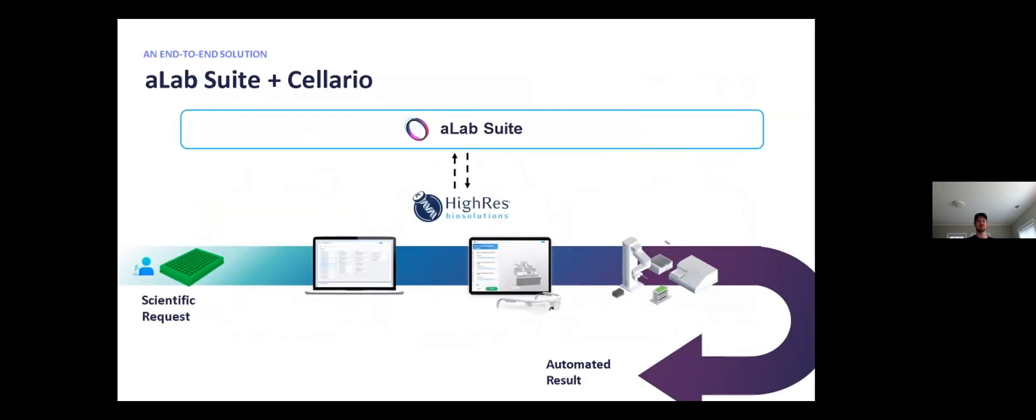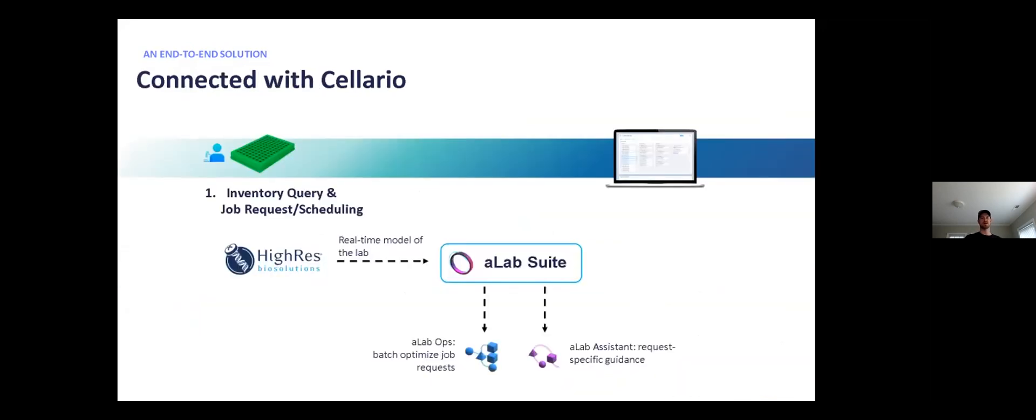So now that you have an understanding of how A-Lab Suite works as a whole, we'll dive into the specifics of how A-Lab and Cellario work together to drive automation. To start, when a user batches or schedules a job in A-Lab, the first thing we need to do is understand the state of the work cell. We do this by using the Cellario services API to query the inventory and mirror this state into our A-Lab digital twin.